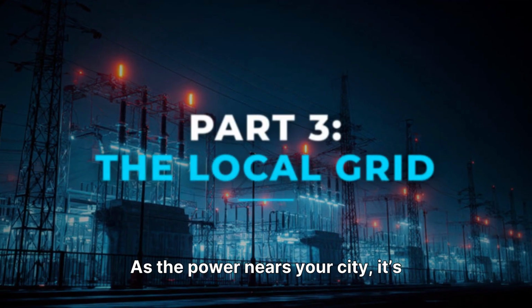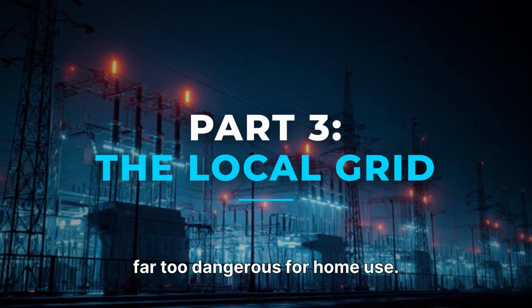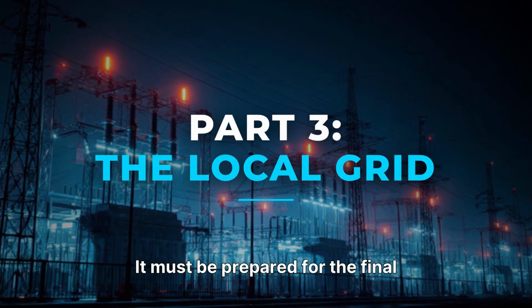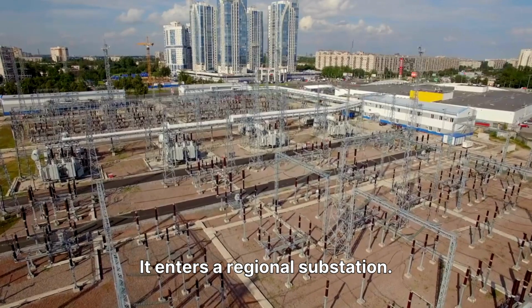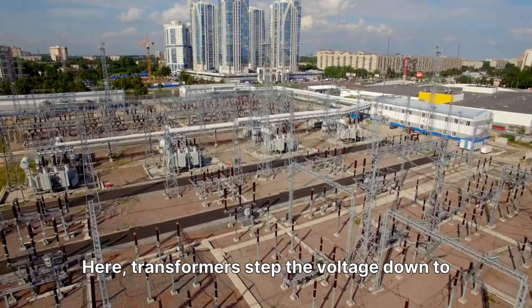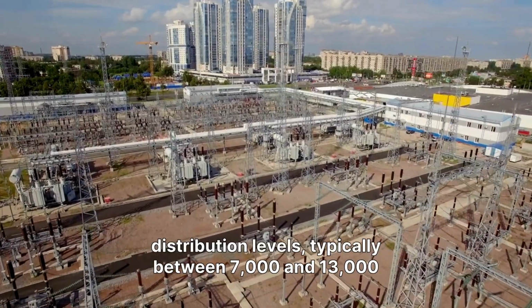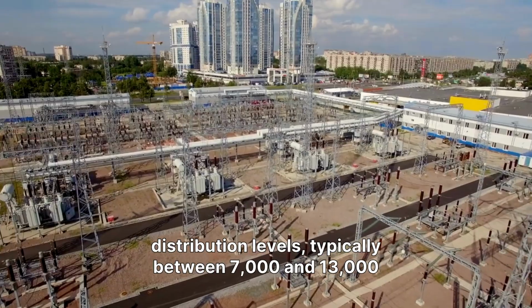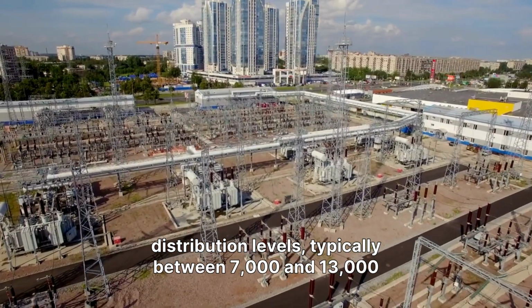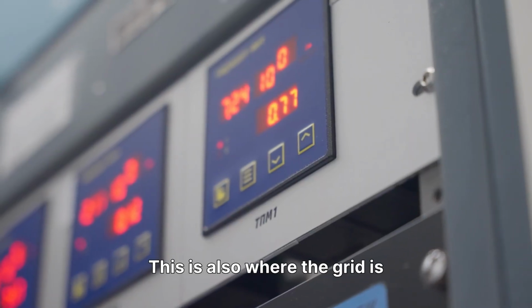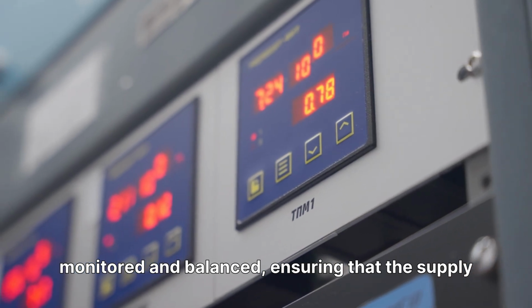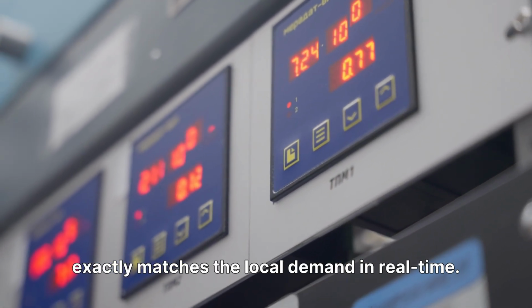As the power nears your city, it's far too dangerous for home use. It must be prepared for the final neighborhood journey. It enters a regional substation. Here, transformers step the voltage down to distribution levels, typically between 7,000 and 13,000 volts. This is also where the grid is monitored and balanced, ensuring that the supply exactly matches the local demand in real time.